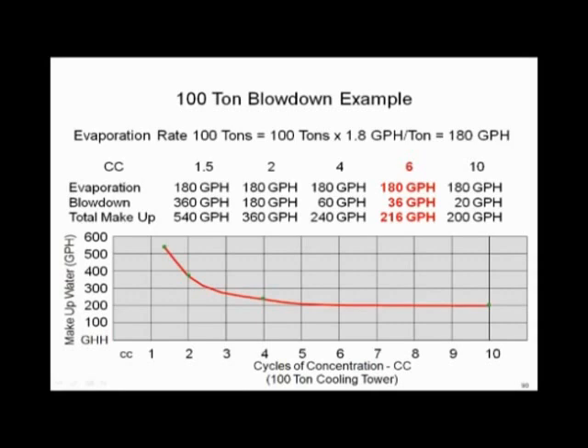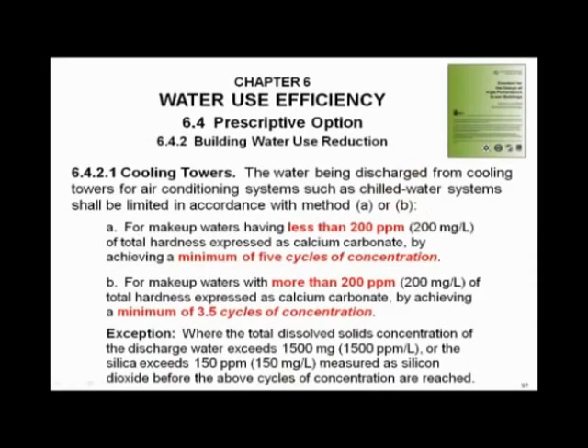So what are reasonable cycles of concentration to specify? ASHRAE 189.1 — the green building code adopted by the Army Corps of Engineers and many cities — defines cycles of concentration for the first time. If you have less than 200 parts per million of solids in your water, a minimum of five cycles of concentration is required. If you're in the west with hard water over 200 parts per million, three and a half cycles applies. The point is you're going to be asked to control your blowdown rates based on cycles of concentration.